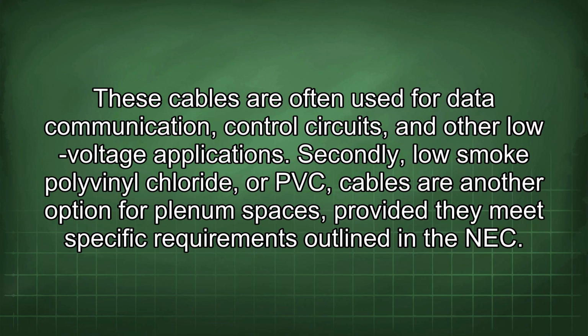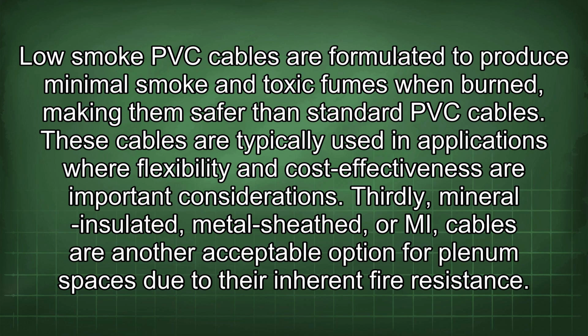Secondly, low-smoke polyvinyl chloride, or PVC, cables are another option for plenum spaces, provided they meet specific requirements outlined in the NEC. Low-smoke PVC cables are formulated to produce minimal smoke and toxic fumes when burned, making them safer than standard PVC cables. These cables are typically used in applications where flexibility and cost-effectiveness are important considerations.